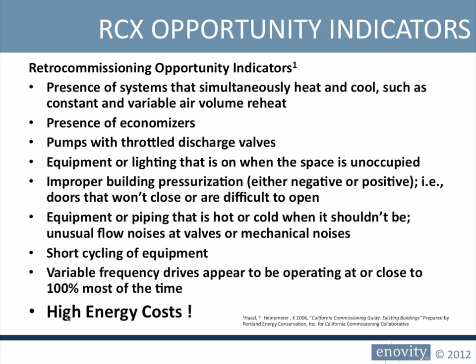So here's some typical measures, and depending on how technical you are, you might appreciate this slide or not. Reducing the supply fan operating schedule, adjusting the air side economizers' dead bands. These are some set point control sequencing strategies for duct supply air temperature set point and duct static. Getting VFDs operating or adding them. A lot of times they're on an override. They're just operating at a constant speed. Just enabling them or re-enabling the sequence that they were intended to modulate.